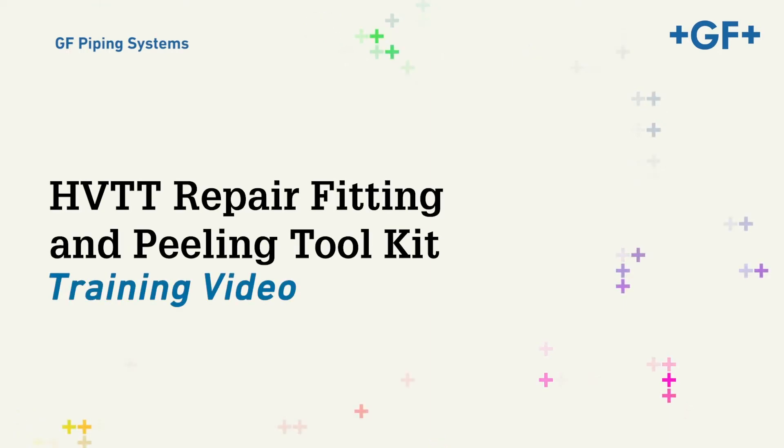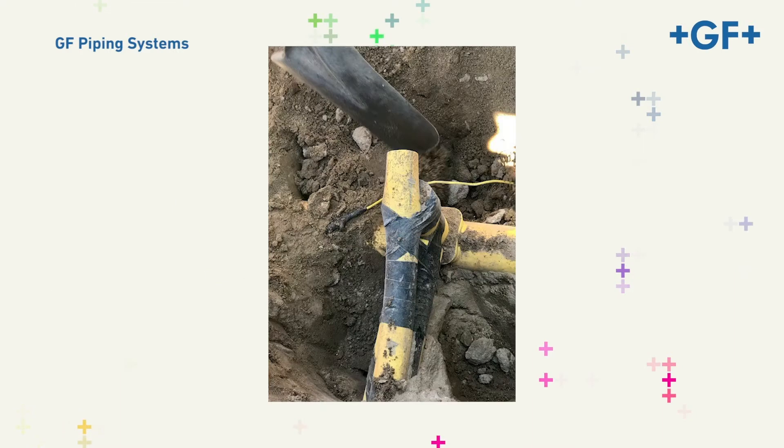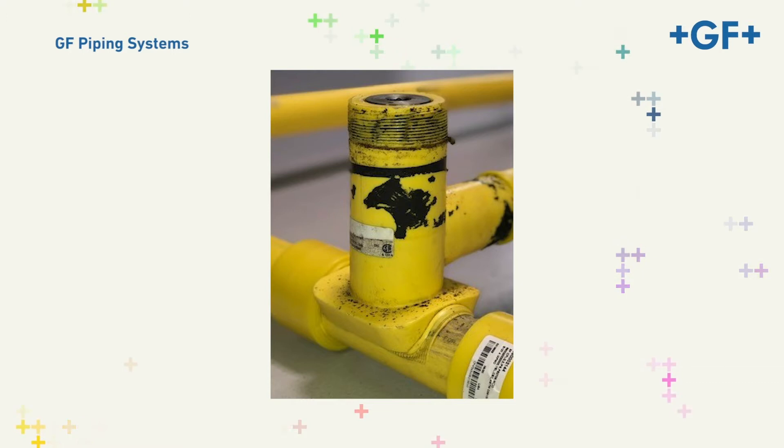In this video, we'll demonstrate the operation instructions for the GF Central Plastics HVTT Repair Fitting and Peeling Toolkit. This repair fitting and toolkit has been designed for use to repair the Uponor Conventional Saddle Fusion High Volume Tapping T-Cap. It can be used in cases where the cap is damaged and cannot be tightened, or when replacement with an OEM cap is not possible. This cap repair system contains a tool specifically designed to remove the threads by peeling the tower of the HVTT to accept the Electrofusion HVTT Repair Fitting.